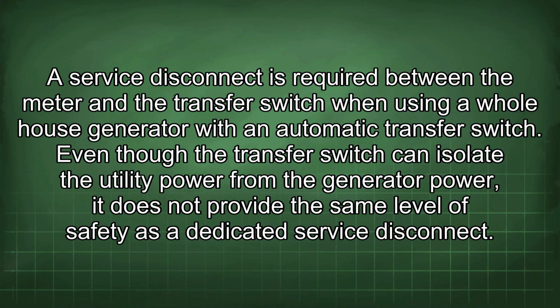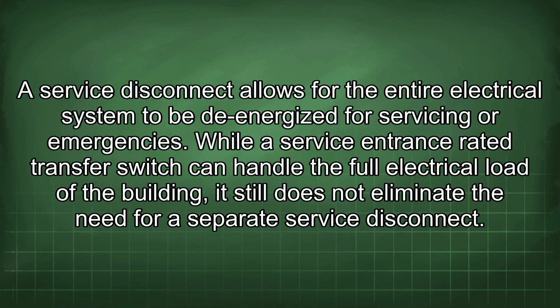A service disconnect is required between the meter and the transfer switch when using a whole house generator with an automatic transfer switch. Even though the transfer switch can isolate the utility power from the generator power, it does not provide the same level of safety as a dedicated service disconnect. A service disconnect allows for the entire electrical system to be de-energized for servicing or emergencies.